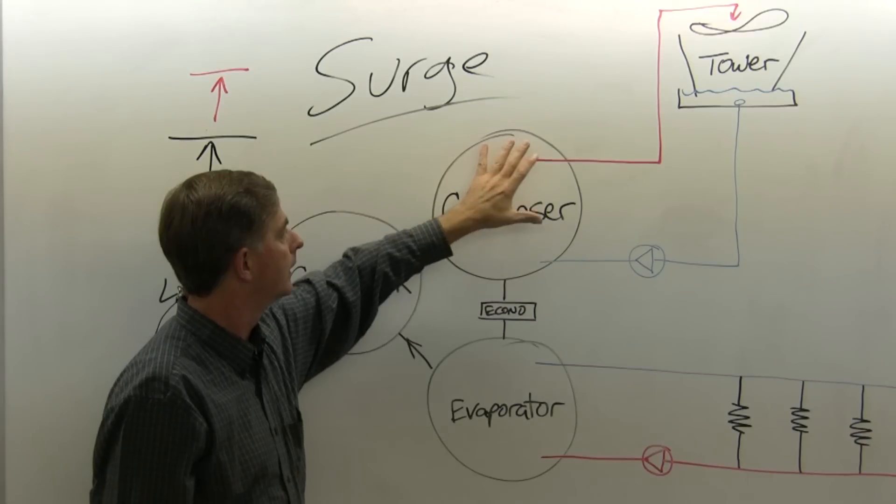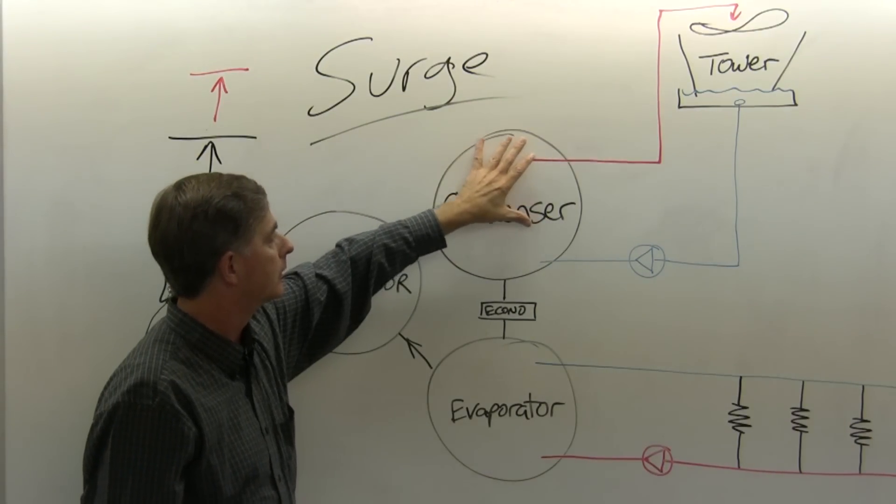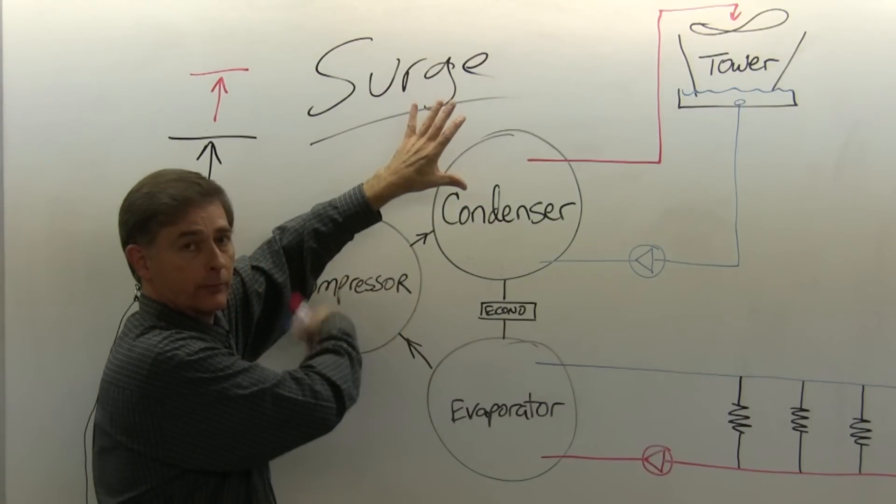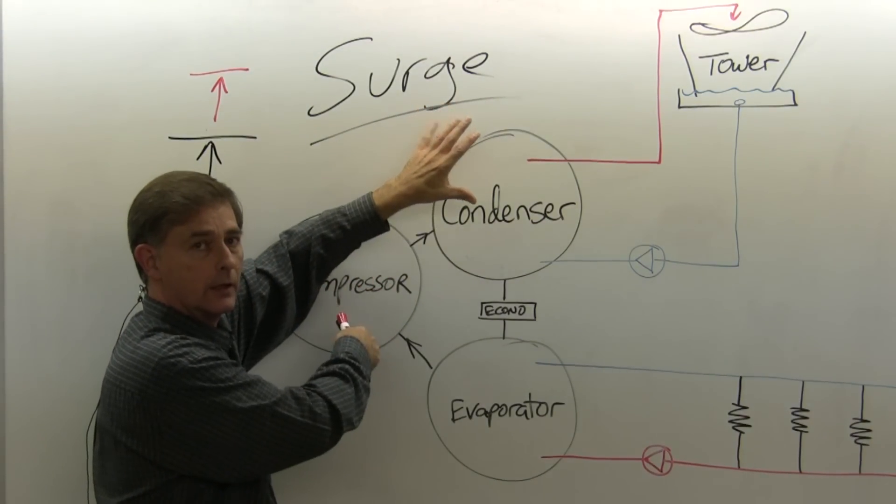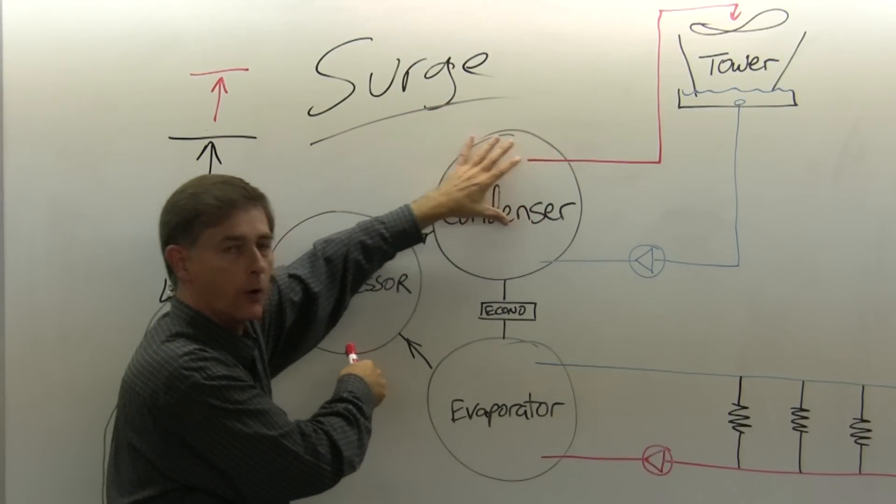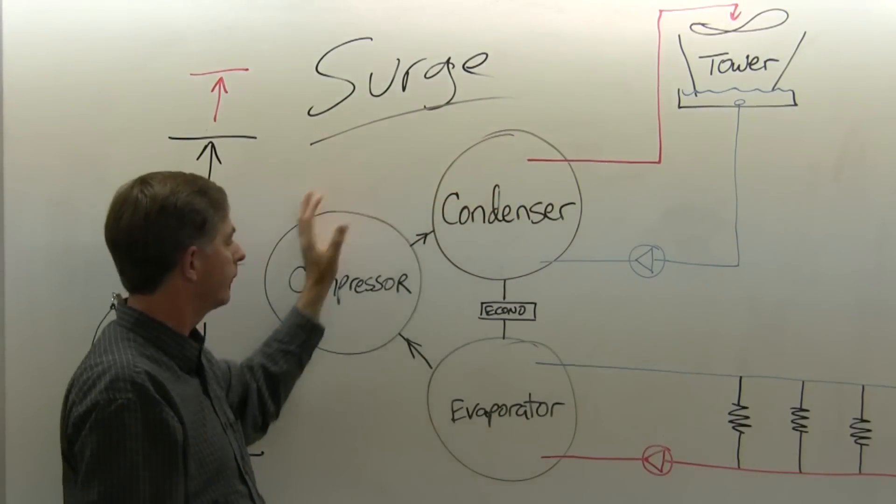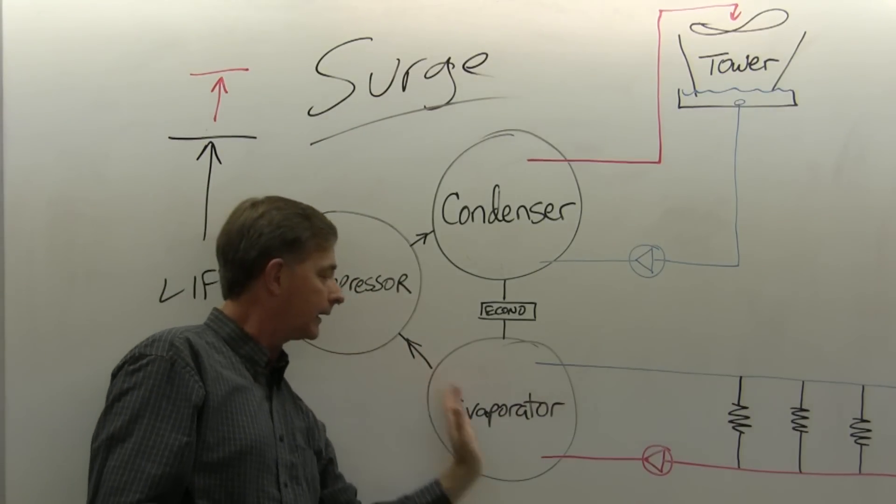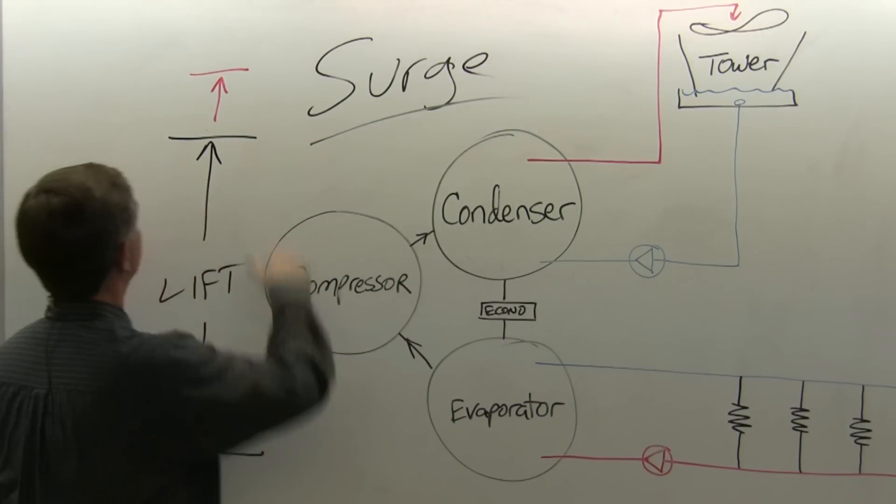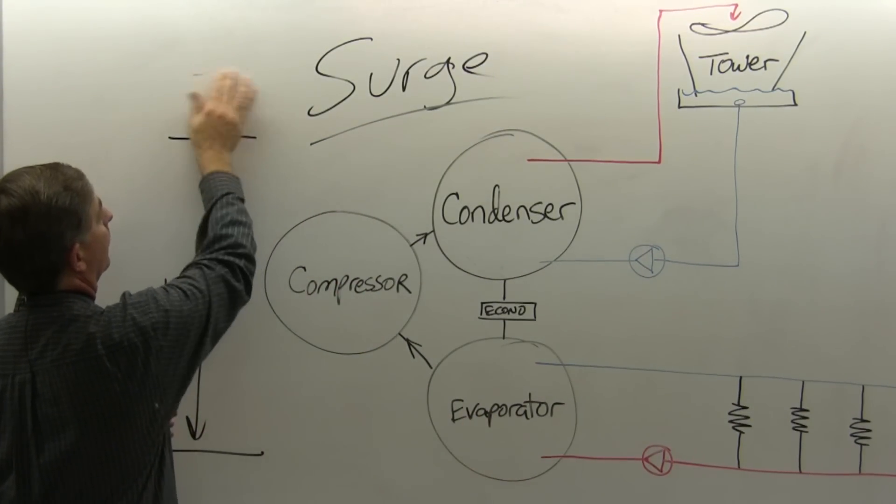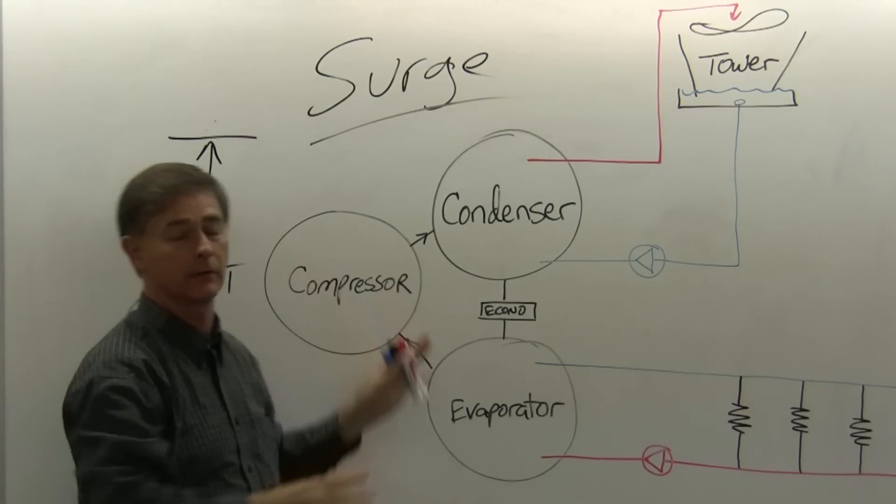And what happens is, although the compressor is turning, the pressure will go backwards through that spinning impeller, it goes backwards through this system, and into the evaporator, which drops our pressure differential, and then it settles out.